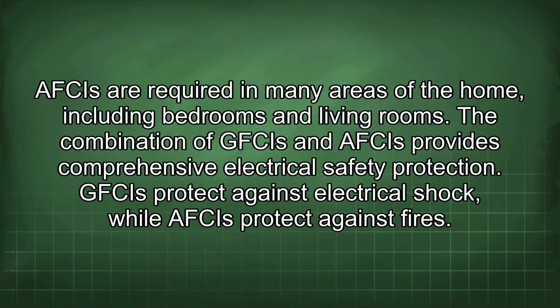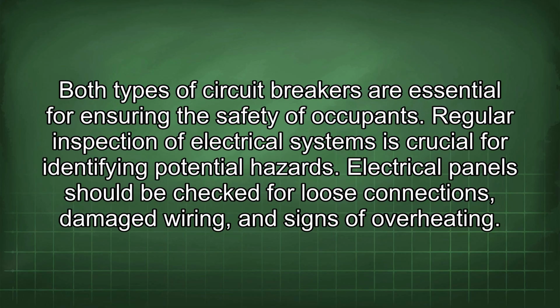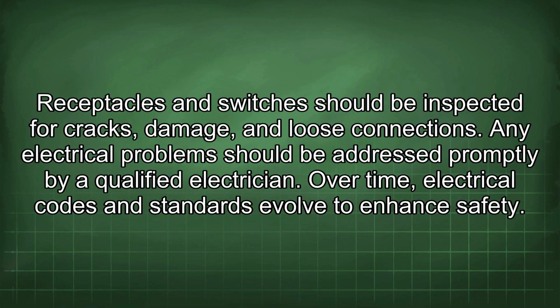The combination of GFCIs and AFCIs provides comprehensive electrical safety protection. GFCIs protect against electrical shock, while AFCIs protect against fires. Both types of circuit breakers are essential for ensuring the safety of occupants. Regular inspection of electrical systems is crucial for identifying potential hazards. Electrical panels should be checked for loose connections, damaged wiring, and signs of overheating. Receptacles and switches should be inspected for cracks, damage, and loose connections.